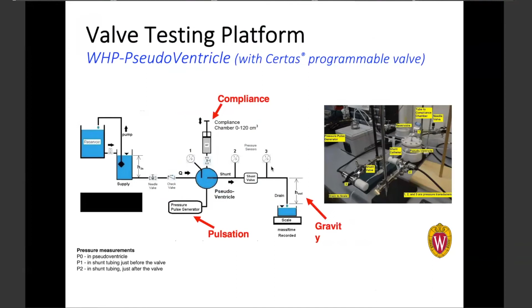So what he built is a valve testing system that has a pseudo ventricle, that has a reservoir, and where you can change the compliance of the system, just like when you change the compliance of the ventricles. You can change the pulsation, frequency, and pulse pressures, and you can change gravity by increasing the height of the tube. So it has all of these parameters that you can change, but it also has 3 ICP sensors. There's 3 pressure sensors. One here in the pseudoventricle, one before the valve, and one after the valve. So armed with this valve testing system, which resides in an engineering building, we've started looking at the Certas valve.